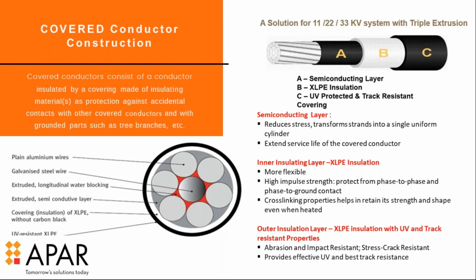Then we have a semiconducting layer, shown in gray. Then a pure XLPE layer, shown in white, and over it another XLPE layer. So there are two layers of XLPE: one pure XLPE, and another black XLPE layer which has UV resistance and track resistance. These are the two important properties required to keep the covered conductor suitable for overhead applications.